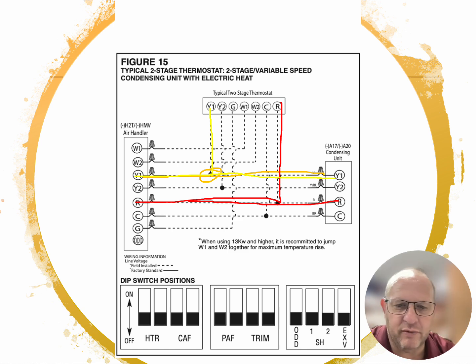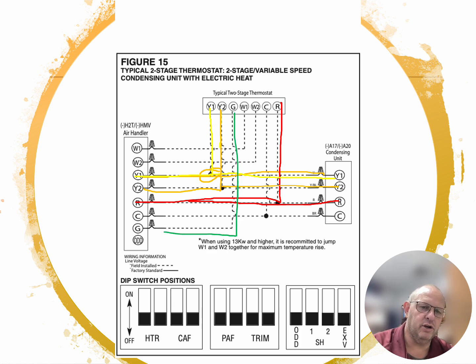After a certain degree has passed, or a certain amount of time, and the indoor unit has not satisfied, the thermostat then will kick on the second stage cooling, which is indicated by that Y2. Y2 will come down. It will power on the indoor unit, and it will power the Y2 on the outdoor unit, providing it with second stage. So either the compressor has a 2-stage solenoid on it, or it has two speeds on it. The two speed compressors have kind of went along the wayside. We are now dealing with solenoid valves on our systems themselves. G will be energized as well, telling the indoor unit to kick on. We see the thermostat has a common, so the common will go to the common on the indoor unit. Plus, we need to bring a common back from the outdoor unit so that those systems will operate perfectly fine.